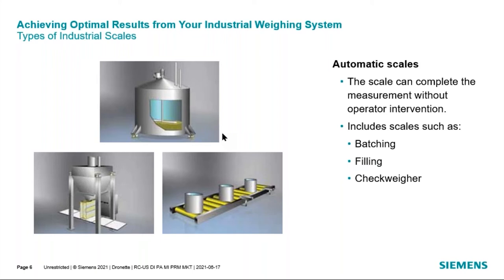Checkweighers are also considered automatic scales. With a checkweighing system, you have a conveyor that transports discrete items — packages of dish detergent or packages of meat. To install a checkweighing system on a roller conveyor, you cut the conveyor in a section long enough to contain a single package and place that section on load cells. The scale electronics determine when the package is completely on the scale as it moves down the conveyor — either via a peak-hold meter or photoeyes to monitor when the package is completely on it.